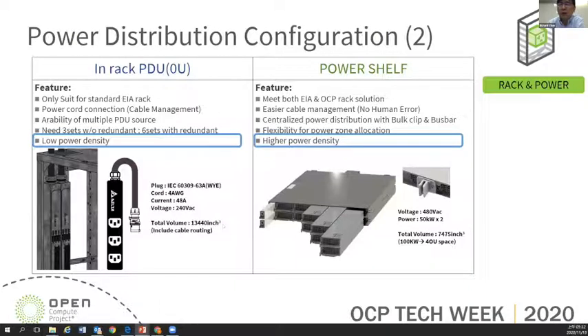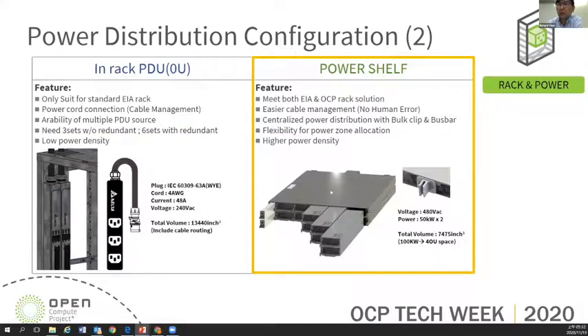After that, we check the power shelf. According to recent industrial technology, for the power density check, we probably need 4 OU to fulfill a 100 kilowatt power shelf. Compared to these two solutions, we find the power shelf, with its higher power density, is our candidate for the design of the high power rack.